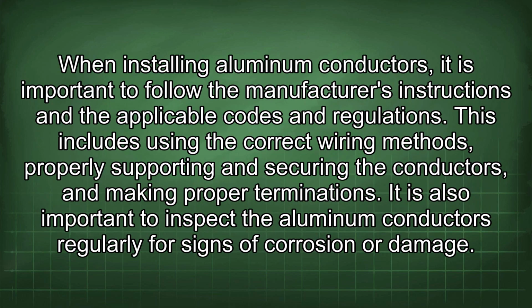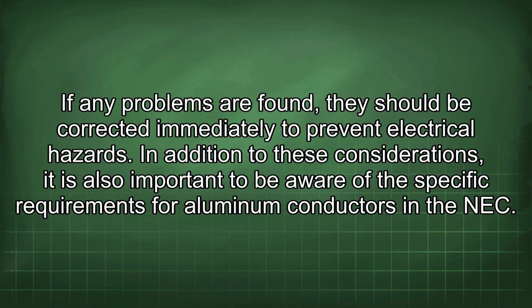When installing aluminum conductors, it is important to follow the manufacturer's instructions and the applicable codes and regulations. This includes using the correct wiring methods, properly supporting and securing the conductors, and making proper terminations. It is also important to inspect the aluminum conductors regularly for signs of corrosion or damage. If any problems are found, they should be corrected immediately to prevent electrical hazards.